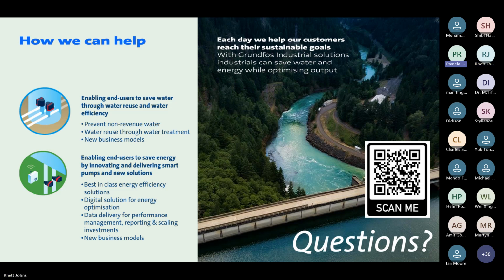Can your sensor systems work on an offline closed network? Absolutely. Yeah. So that's actually a great benefit of a Grundfos system, is that it can operate completely on its own, be it programmed directly on the pumps or on the controller, and you don't have to network back to anything. So you can set this as a distributed control system within your system, and it can operate completely independently without any requirement of feedback from a BMS or anything like that.